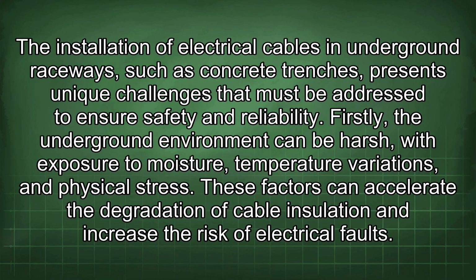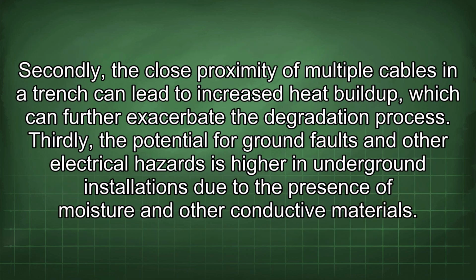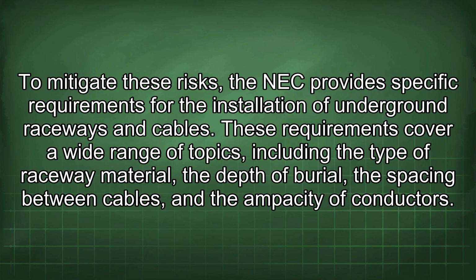The installation of electrical cables in underground raceways, such as concrete trenches, presents unique challenges that must be addressed to ensure safety and reliability. Firstly, the underground environment can be harsh, with exposure to moisture, temperature variations, and physical stress. These factors can accelerate the degradation of cable insulation and increase the risk of electrical faults. Secondly, the close proximity of multiple cables in a trench can lead to increased heat buildup, which can further exacerbate the degradation process. Thirdly, the potential for ground faults and other electrical hazards is higher in underground installations due to the presence of moisture and other conductive materials. To mitigate these risks, the NEC provides specific requirements for the installation of underground raceways and cables. These requirements cover a wide range of topics, including the type of raceway material, the depth of burial, the spacing between cables, and the ampacity of conductors.